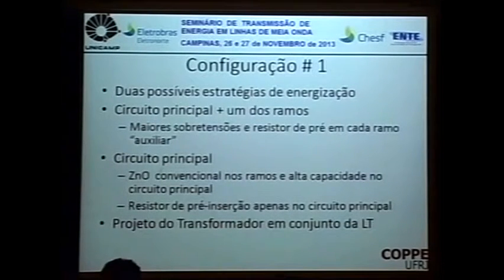There are 2 possible strategies for energization. I energize the main circuit and then one of the branches, or I energize the main circuit, and then after that I start to energize each branch. The requests are going to be different, and I have different efforts both in terms of the circuit breakers and the surge arresters.